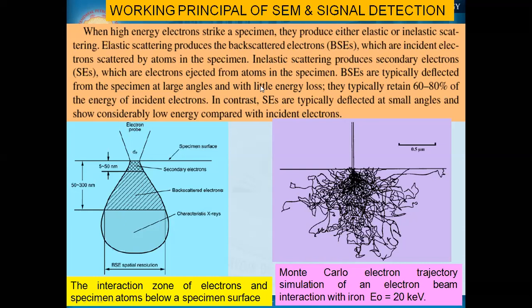Backscattered electrons are typically deflected from the specimen at large angles and with little energy loss — they typically retain 60 to 80% of the energy of the incident electron. In contrast, secondary electrons are typically deflected at small angles and have considerably lower energy compared to the incident electron. So we get two types of electrons: backscattered electrons from elastic scattering, and secondary electrons generated from the atoms of the specimen itself.